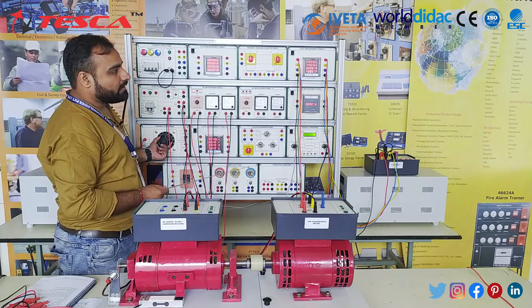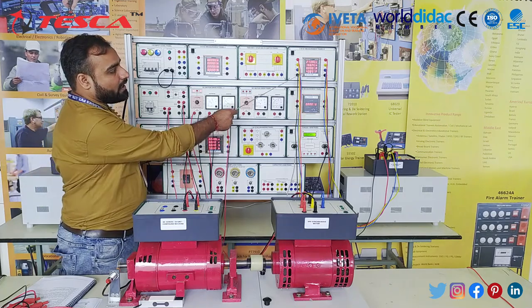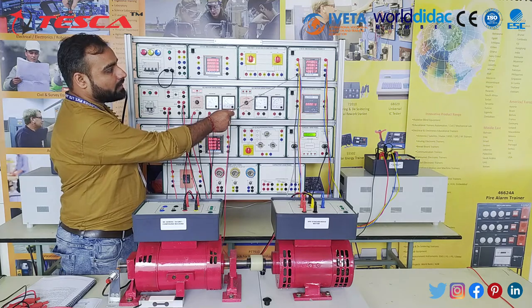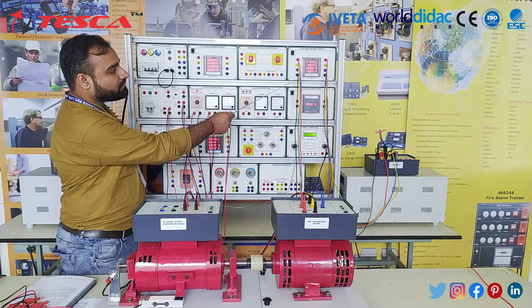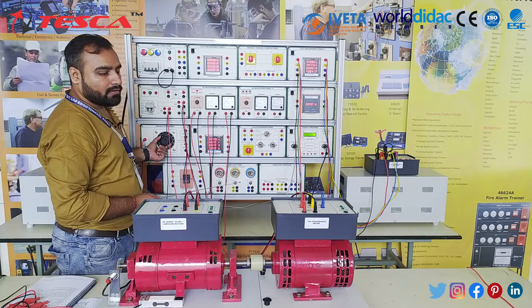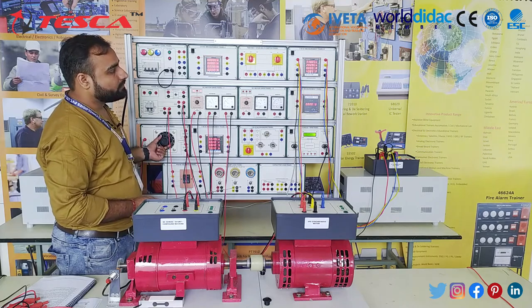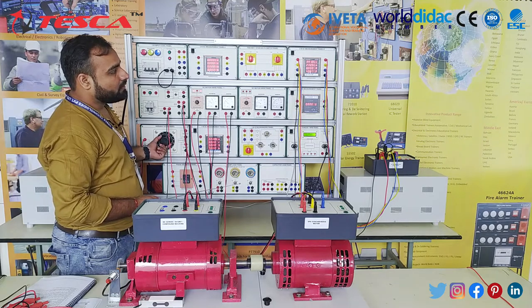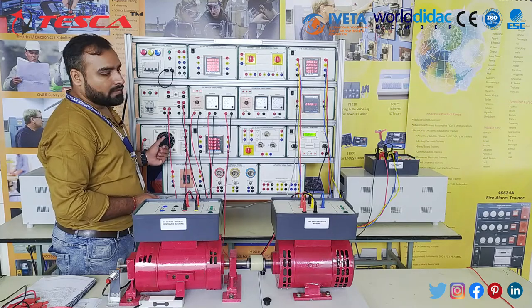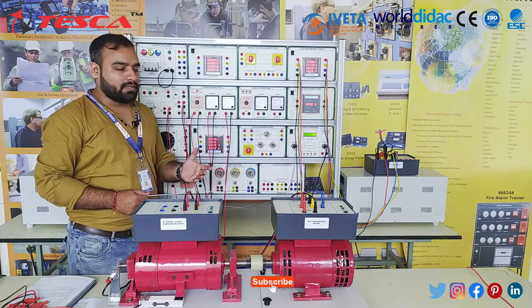You can gradually increase the supply till you get line to line voltages of about 400 volts and line to neutral voltages of about 230 or 240 volts. So here we are now about to reach 400 volts output. Here the output is generated by the synchronous generator.